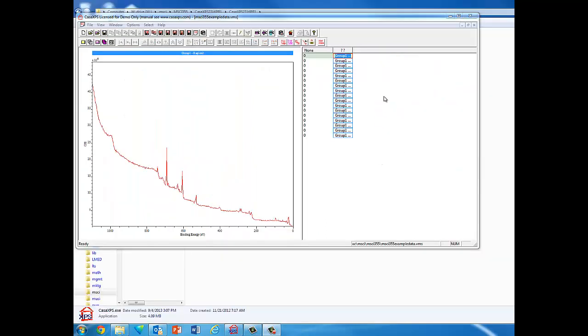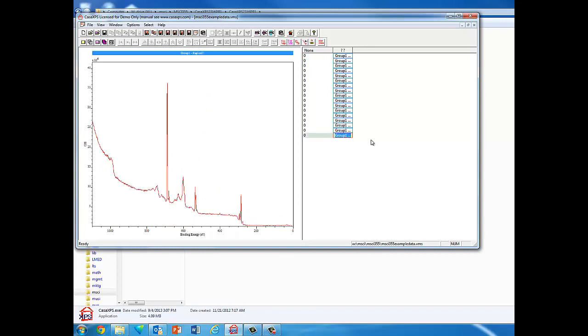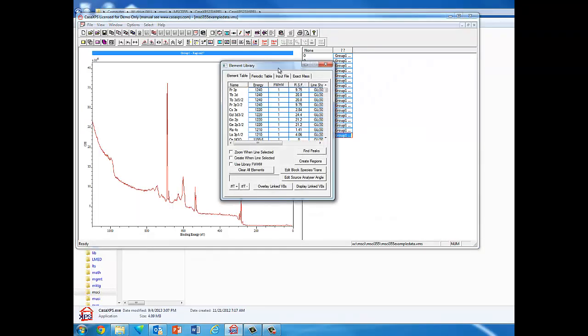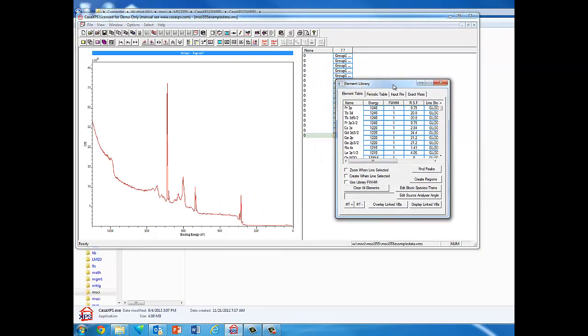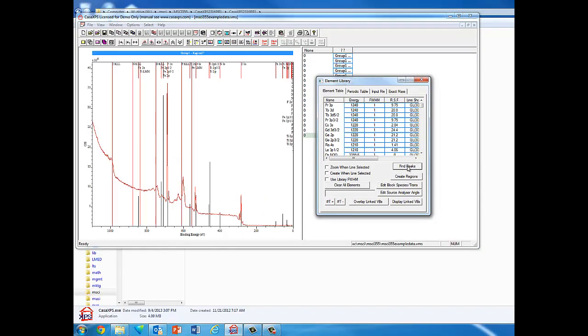Let me review how to identify peaks. If we load the data as shown previously, we can go through and select this last group here to see the peaks. If we want to identify the peaks, we click on the spectrum and then select Library. I'll just leave the element table up, and if I do Find Peaks it automatically goes through and finds the different peaks.